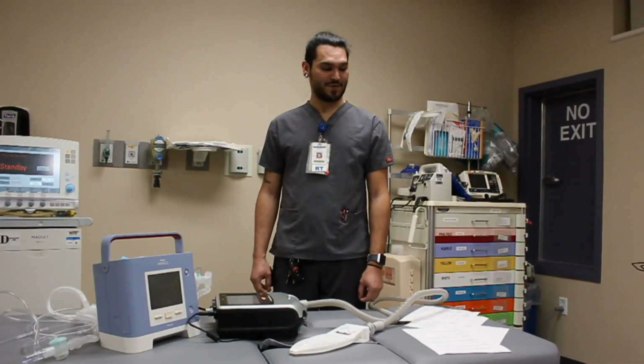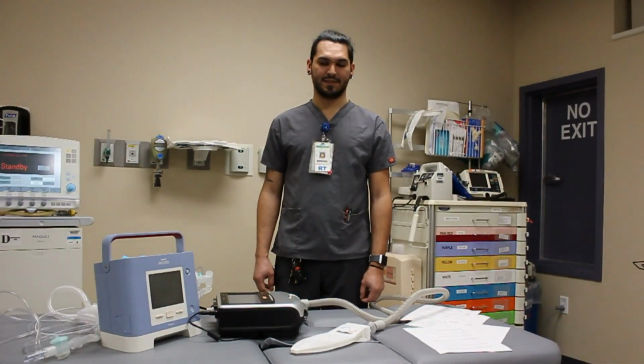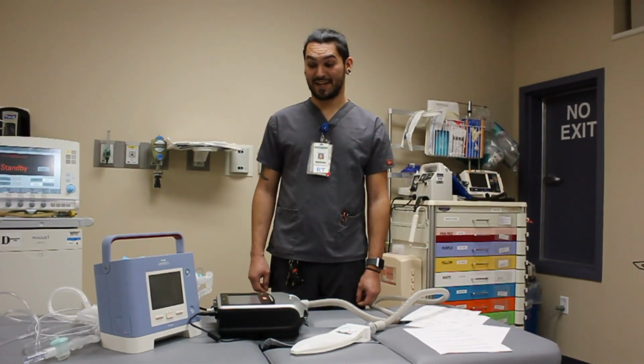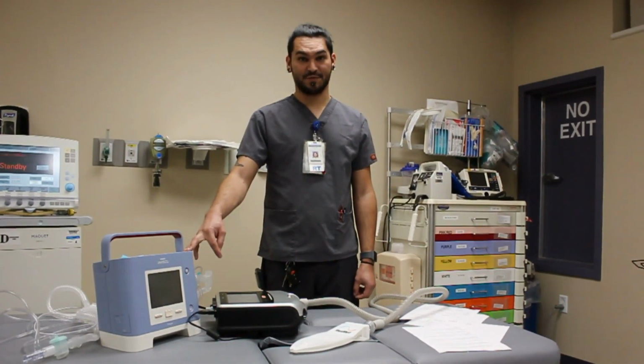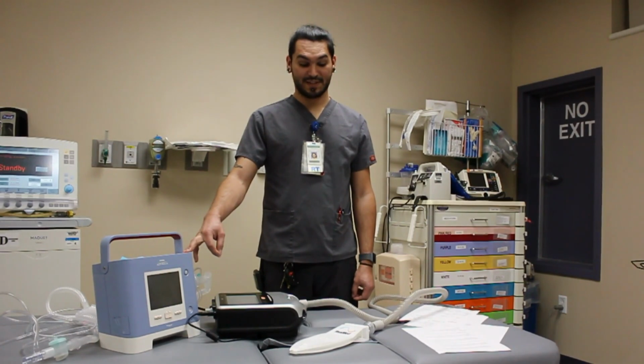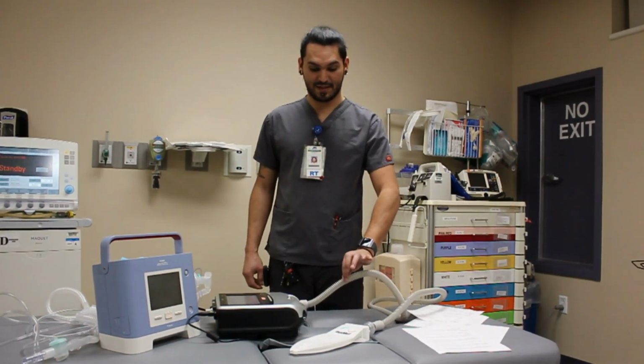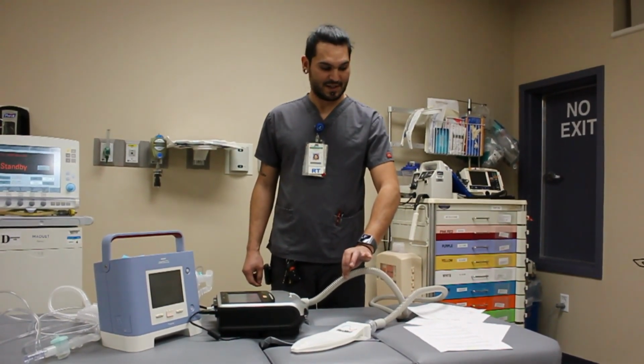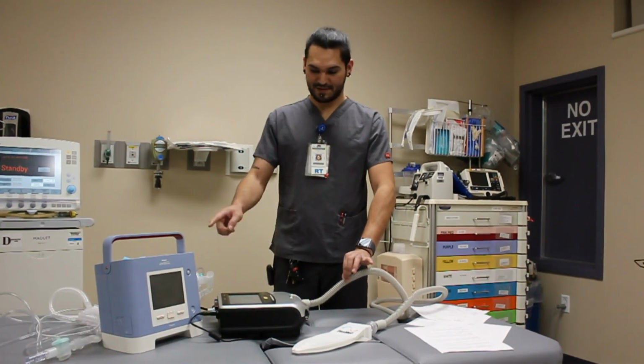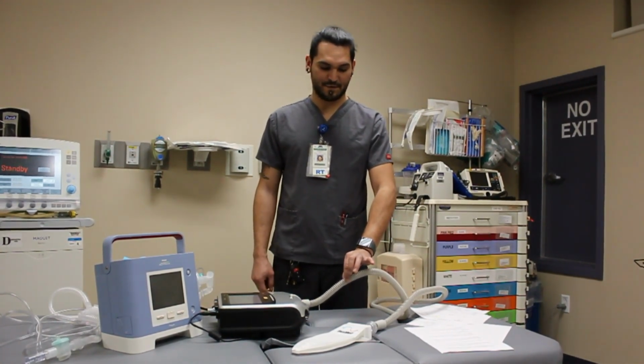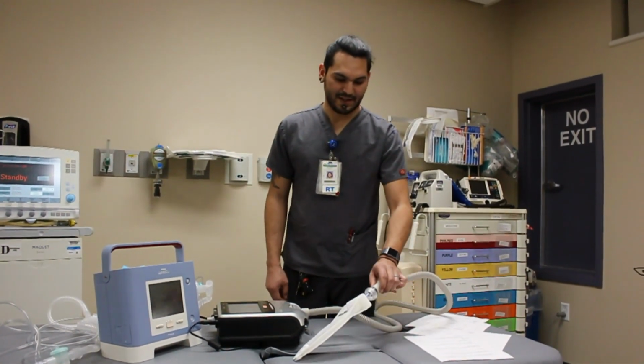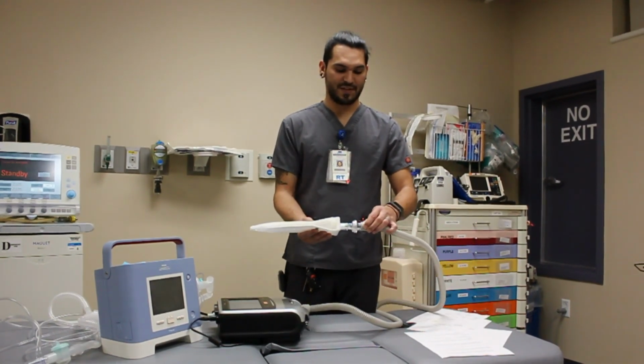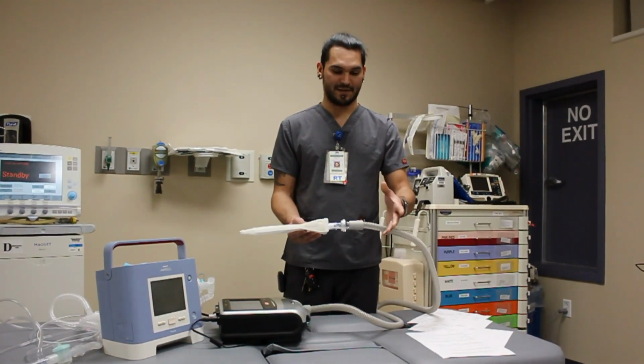Another alarm to go over is the low circuit leak alarm. That one we'll usually find on our home vents, our Trilogy and our Astral. And you will normally see this on any vent that has a single limb circuit. Now, all of these vents on single limbs have a whisper valve that allows your patient to breathe out. It allows gas to escape from here.